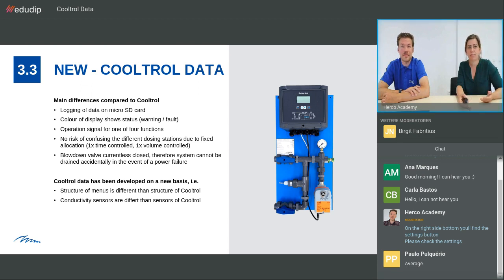Yes. We have the operation signal, as I said. So for blowdown, for release of the dosing pump and the 2 dosing options, we can put out a signal to say on or off, to log it also in the central system. There's no risk, as we said, to confuse the different dosing stations due to the fixed allocation of time and volume control. And we have a new blowdown valve, which is currentless closed. That means if the conditions on site are such that the basin of the cooling tower could run dry because everything runs out through the blowdown valve, then you are safe in case of emergency, let's say power failure, because the blowdown valve will always close when it's currentless.